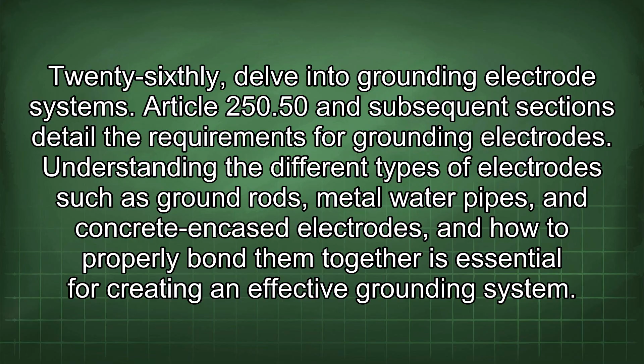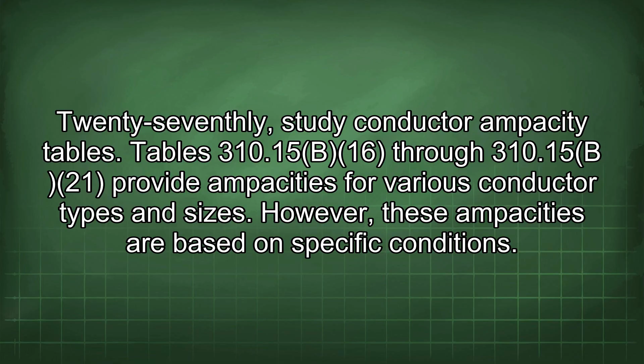27th, study conductor ampacity tables. Tables 310.15(B)(16) through 310.15(B)(21) provide ampacities for various conductor types and sizes. However, these ampacities are based on specific conditions. You must apply correction and adjustment factors based on ambient temperature and the number of current-carrying conductors in a raceway.